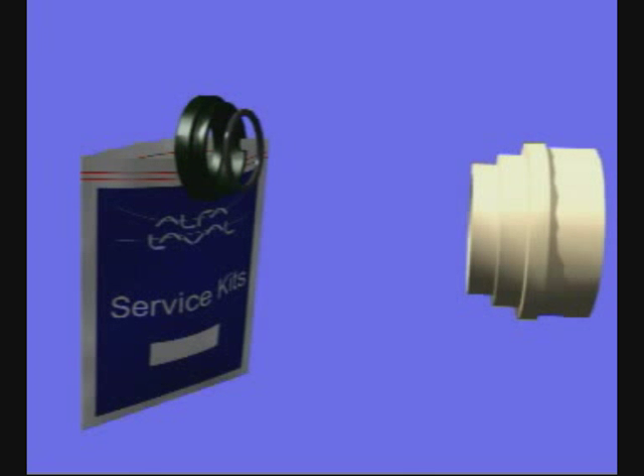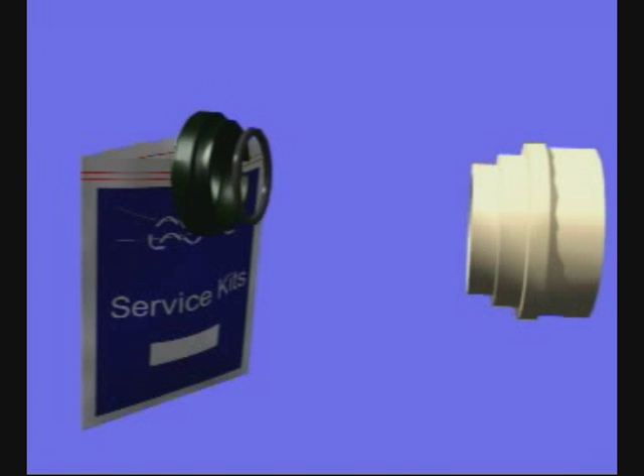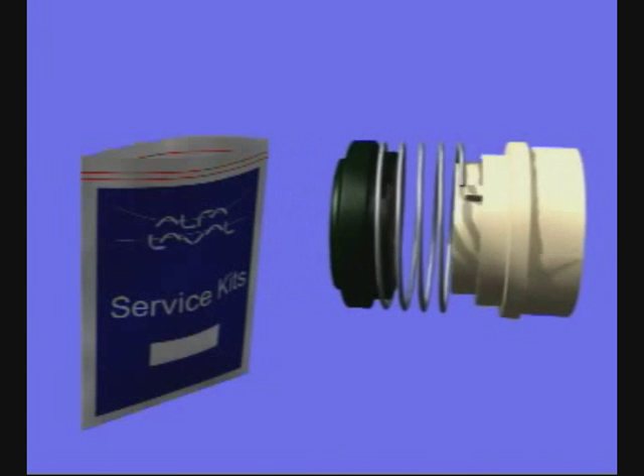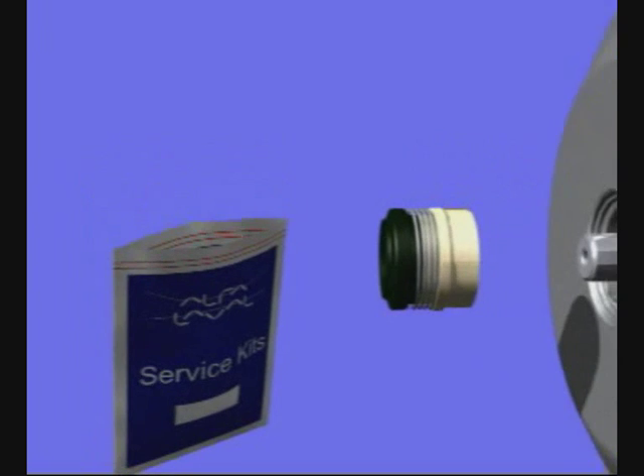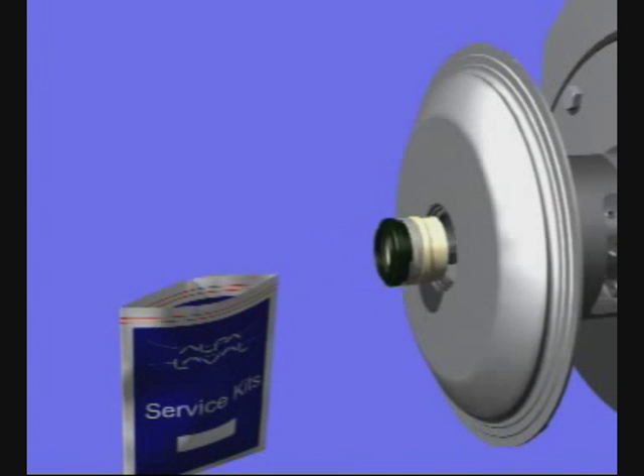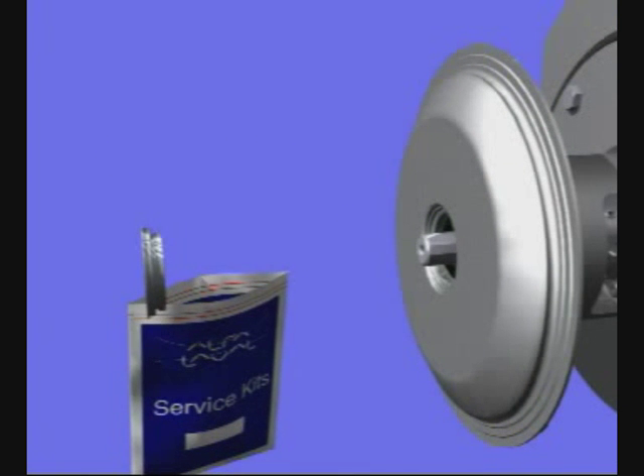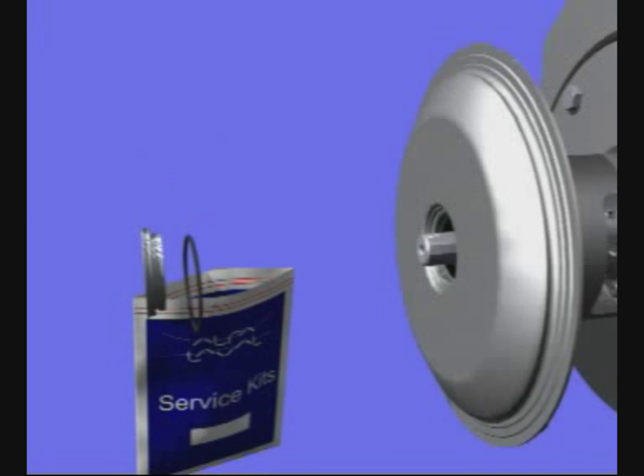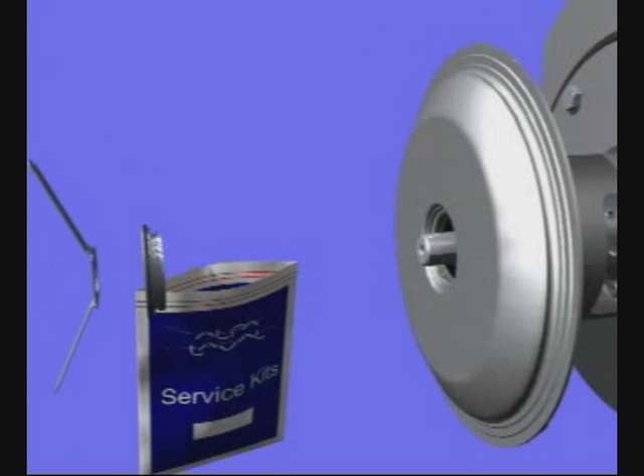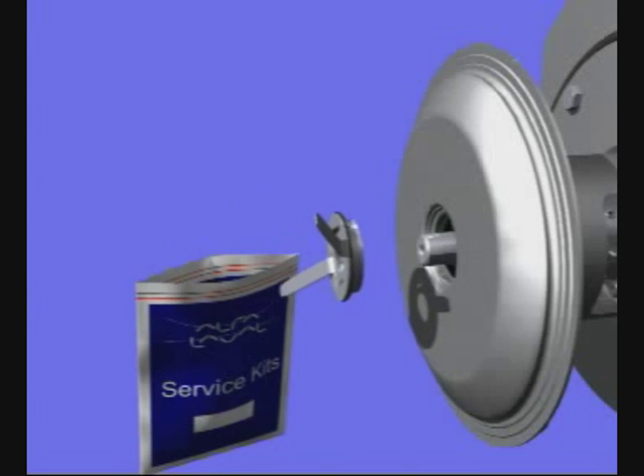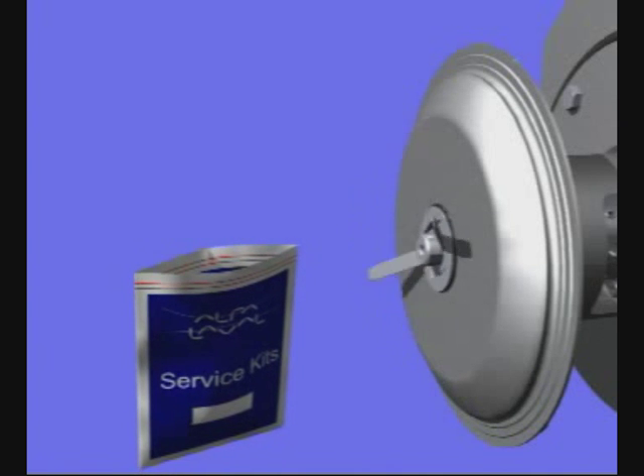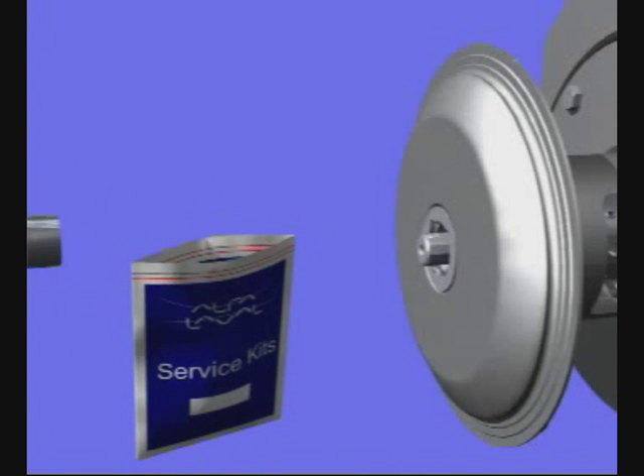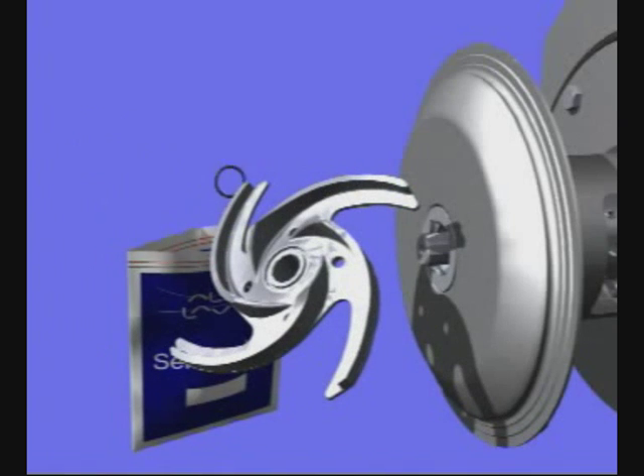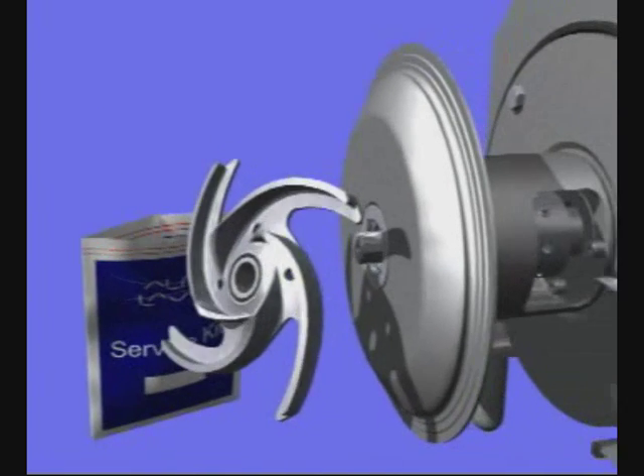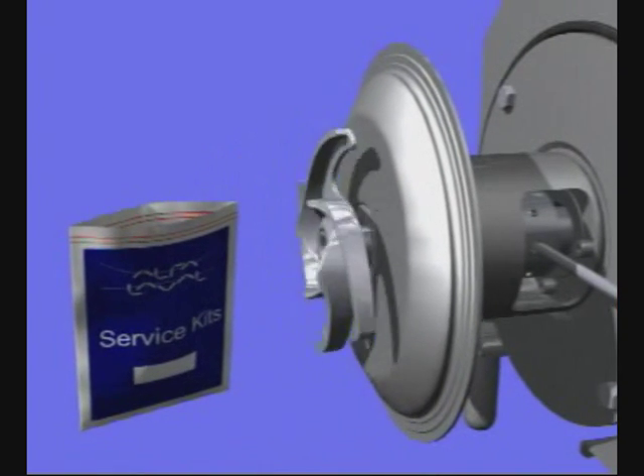When assembling the rotating part of the shaft seal, make sure that the drive ring pin enters the notch on the rotating seal ring. Fit the O-ring on the stationary seal ring and screw it into the back plate. Always lubricate O-rings with food-grade grease or oil before mounting. As for the disassembly, you fix the shaft with a screwdriver.